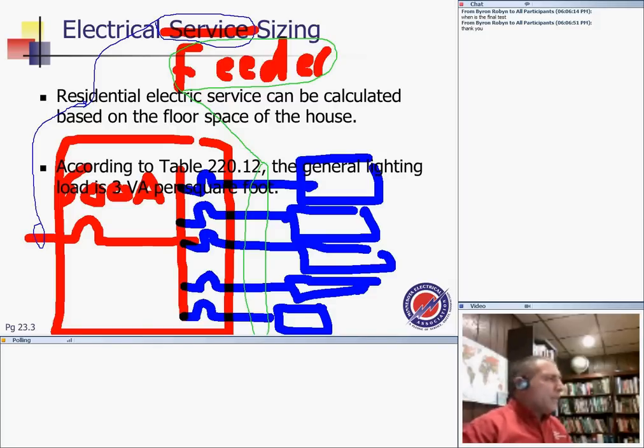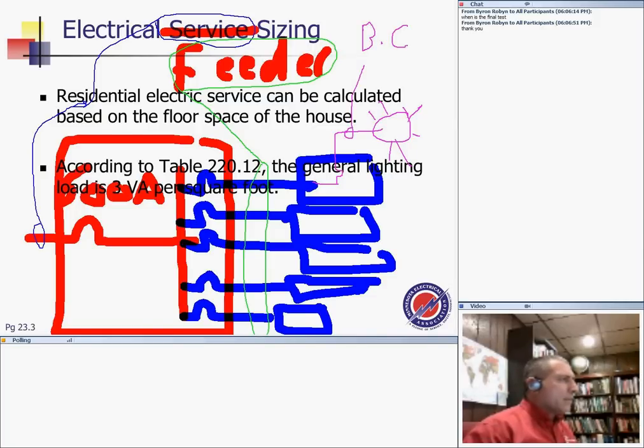Any question, guys, about definition of a service or a feeder? What you're looking at in residential or commercial, that's really no different. These are service conductors and feeders. And just to clarify a little bit, if you take a 20 amp circuit right in here, you could feed your lights, let's say this is a bunch of lights, from a 20 amp circuit. Now this conductor here is going to be a branch. That's what we call a branch circuit, right?